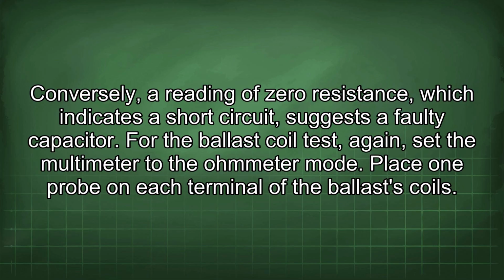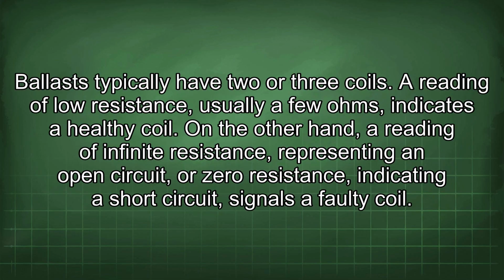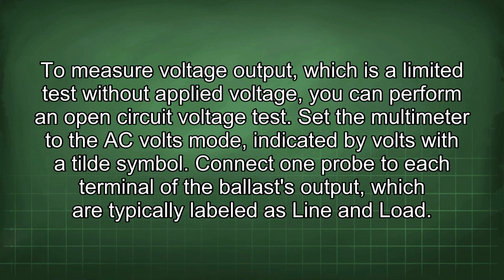For the ballast coil test, again set the multimeter to the ohmmeter mode. Place one probe on each terminal of the ballast coils. Ballasts typically have 2 or 3 coils. A reading of low resistance, usually a few ohms, indicates a healthy coil. On the other hand, a reading of infinite resistance, representing an open circuit, or zero resistance, indicating a short circuit, signals a faulty coil.